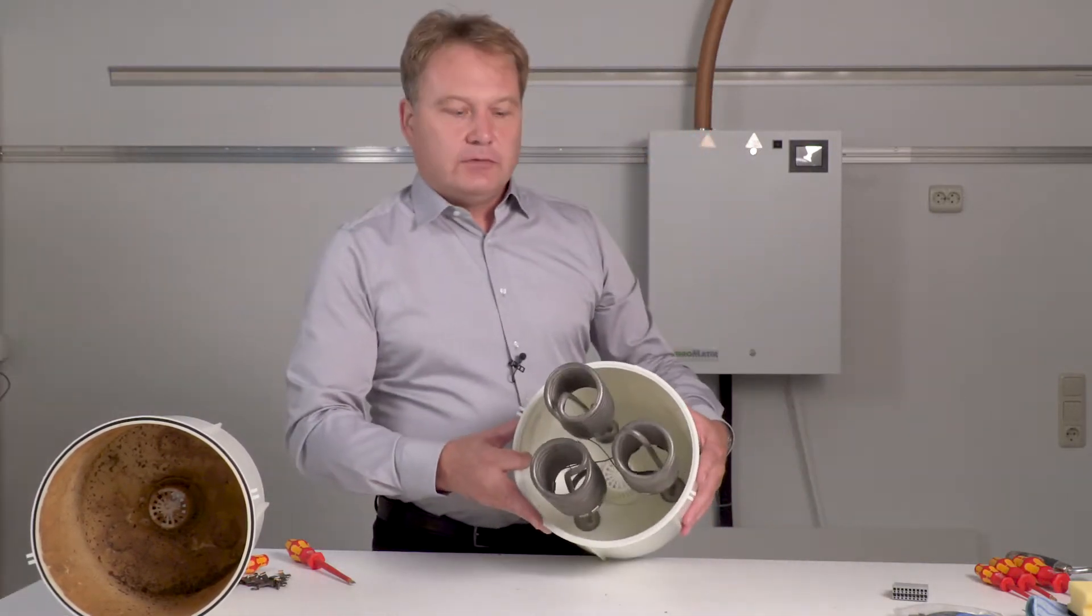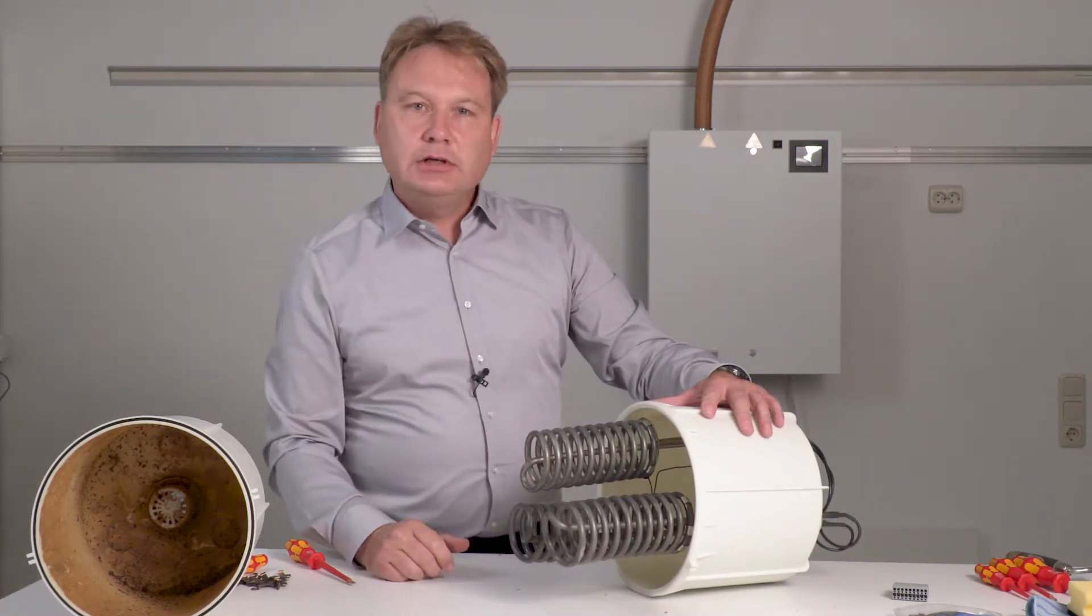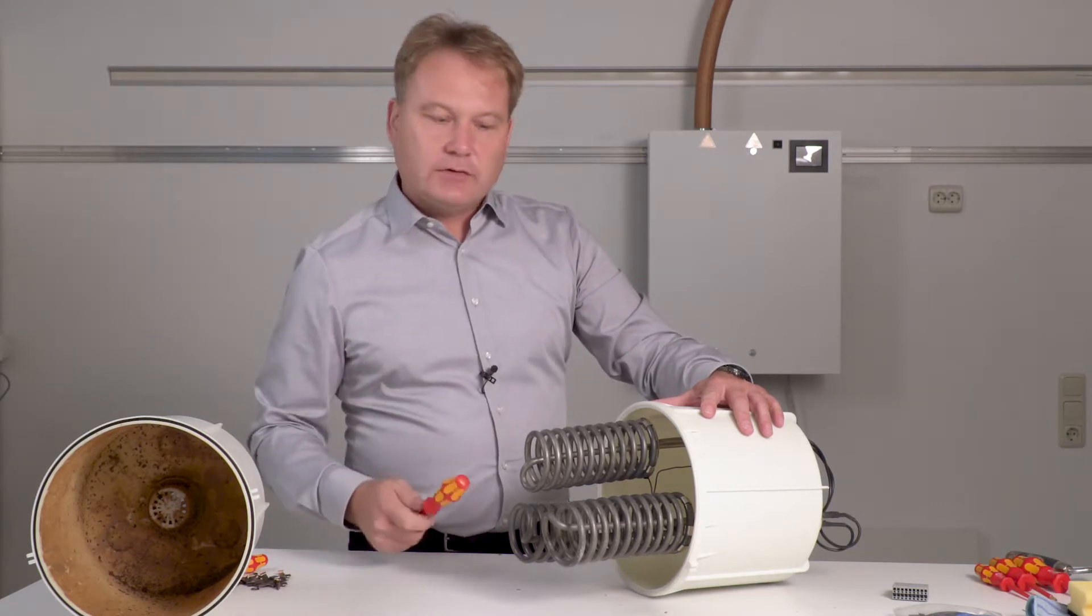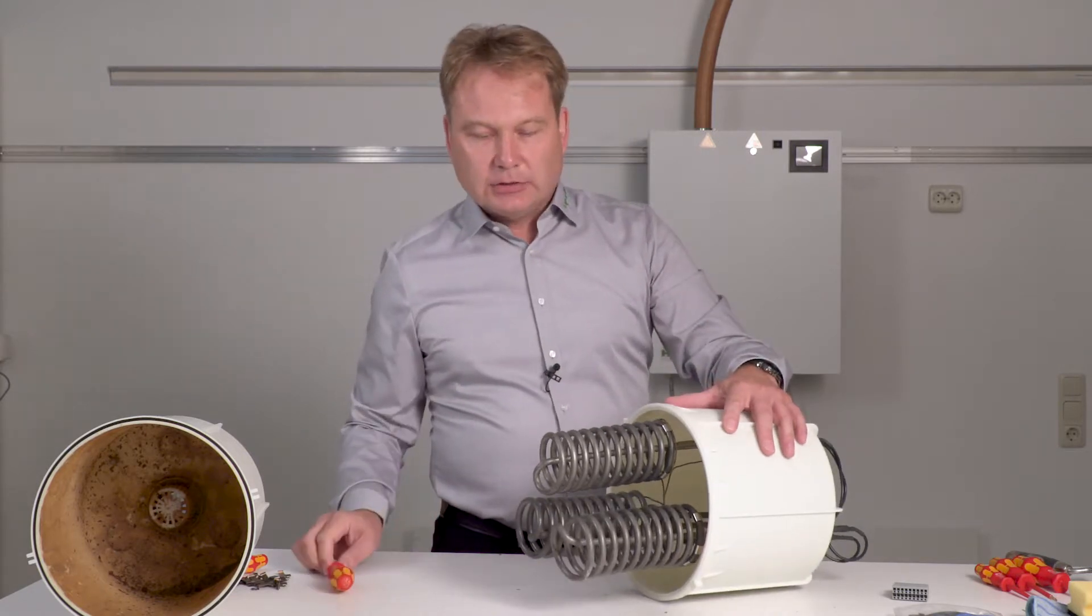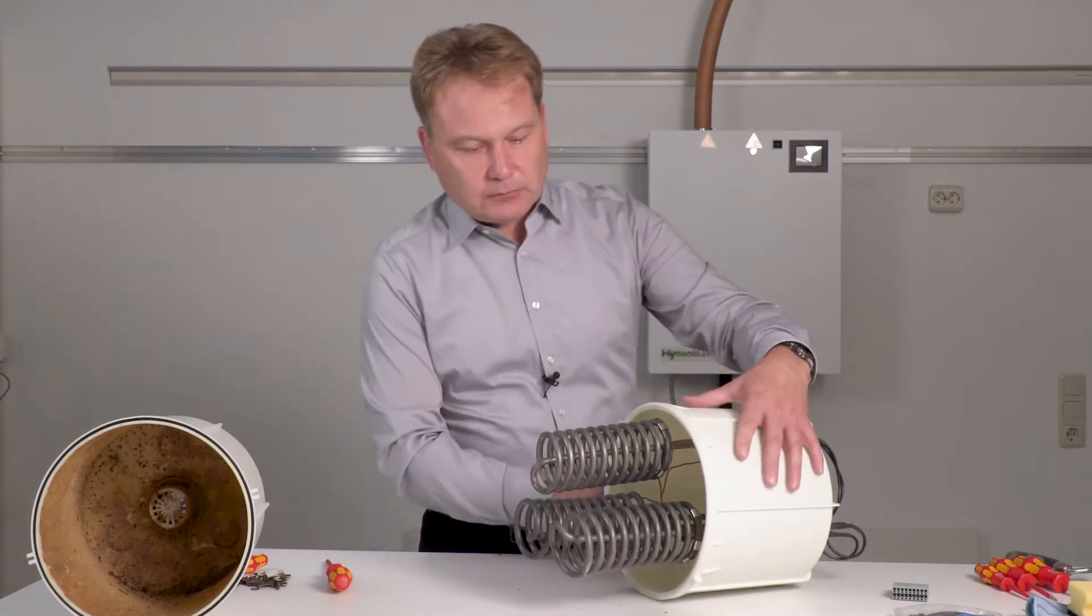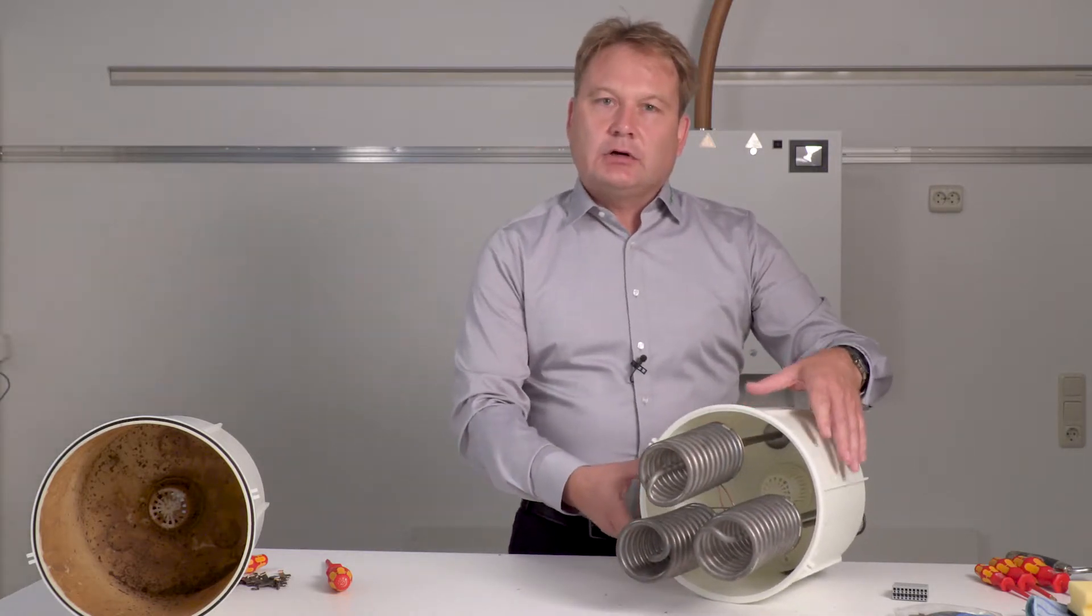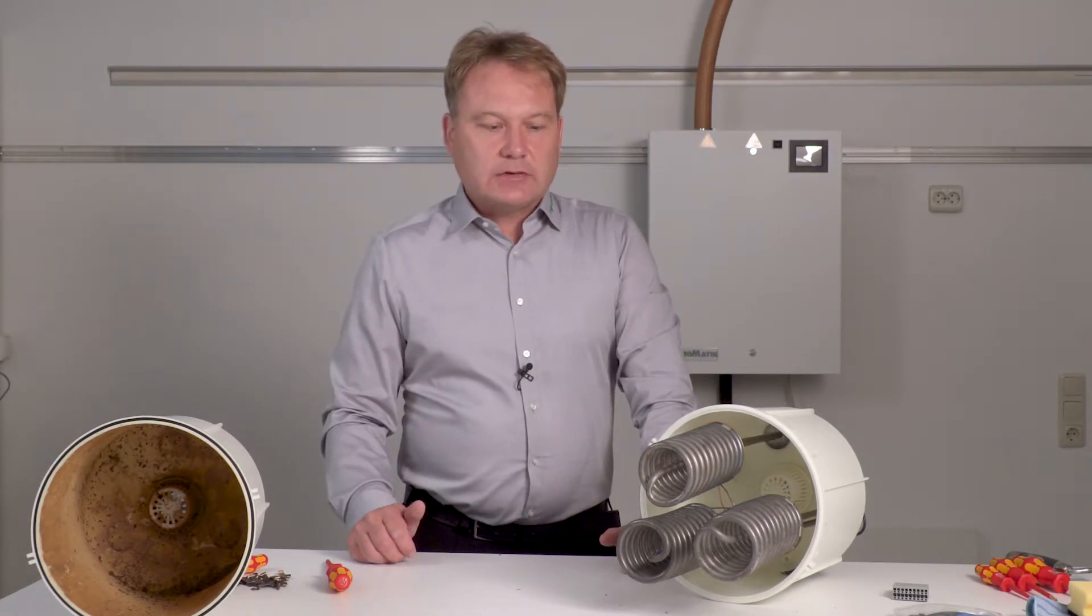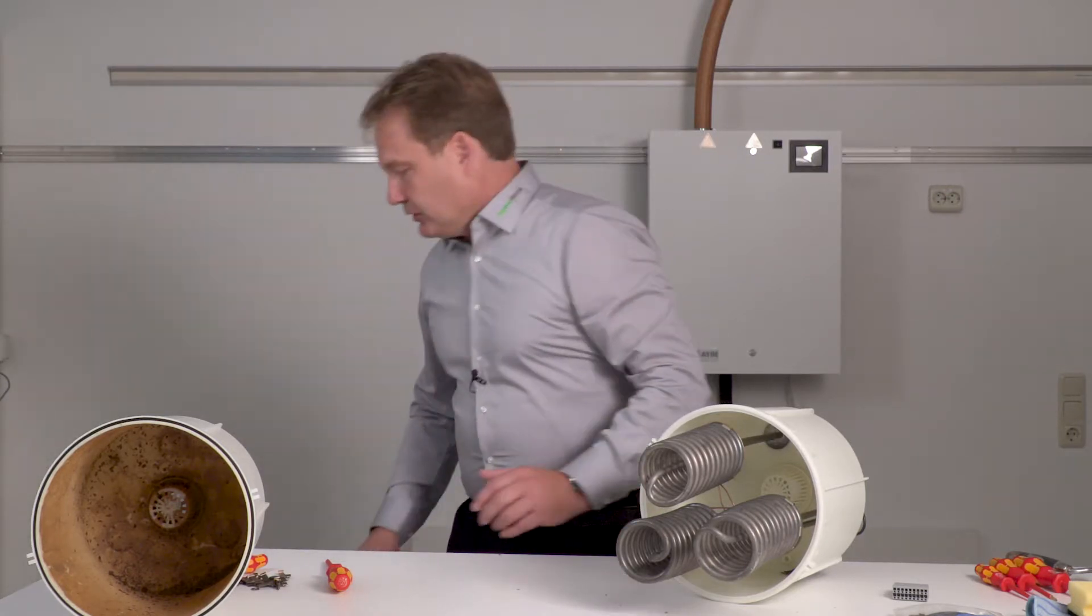In this case, the upper half has three heater elements. If deposits are found here, then take the shaft of the screwdriver and knock on the heater elements carefully so the coarse particles fall off. If the particles can't be loosened, you can use a descaling agent. Citric acid has worked quite well. Please don't use citric acid in concentrations above 10%.